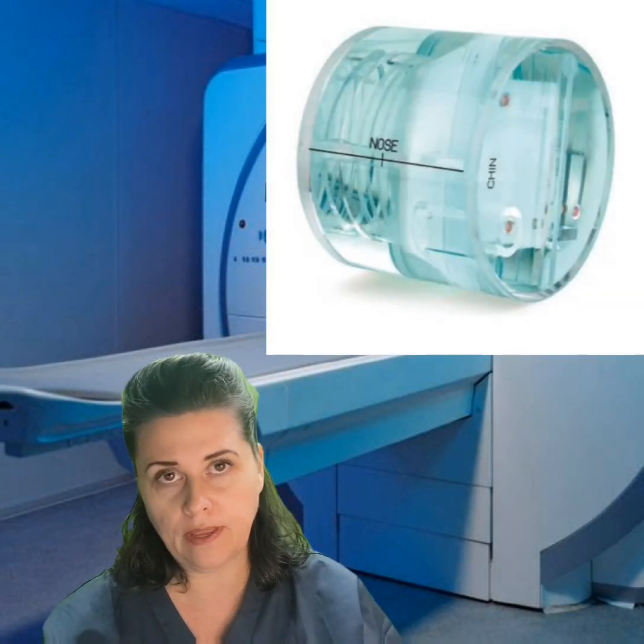ACR, which stands for American College of Radiology, has accreditation. And a part of this accreditation is the so-called phantom. This phantom is used to perform different measurements on the MRI scanner. Simply put, it's a quality control of the equipment, which is the scanner in our case. It makes sure that the scanner performs up to standards and produces high quality images.